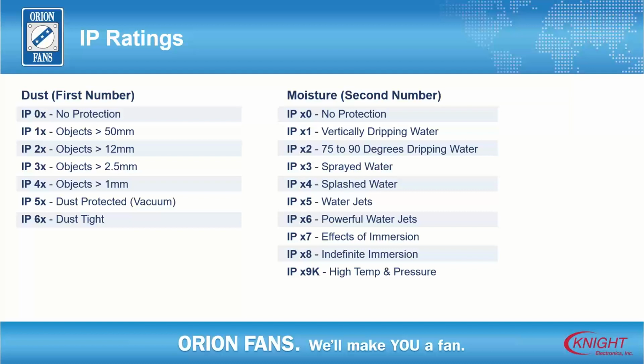The ingress protection of moisture. 0, which is the standard fan that everybody builds, that says, don't get it wet. That's kind of what it is. And then it works its way up. We do it some that are up to a 2, which is basically just a conformal coating. It's not real good. What we try to do is IP55 and up. IP55 is water jets all directions. IP56 is a stronger water jet. IP67 and 68 are immersed. And I've told people, if your fan is underwater, you probably have a bigger problem than the fan being underwater and not working.